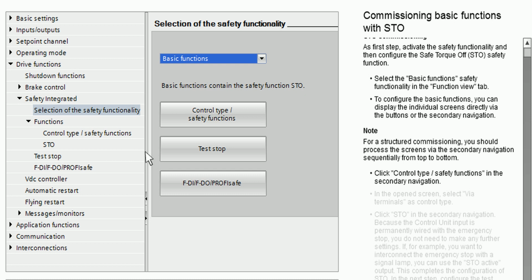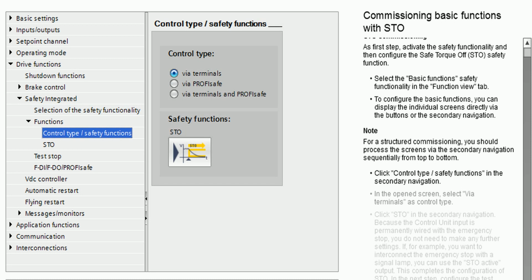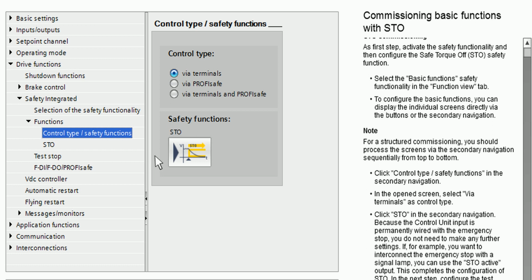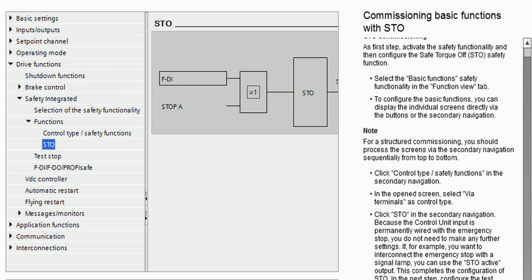Click Control Type, Safety Functions, in the secondary navigation. In the open screen, select Via Terminals as control type. Click STO in the secondary navigation. Because the control unit input is permanently wired with the emergency stop, you do not need to make any further settings.